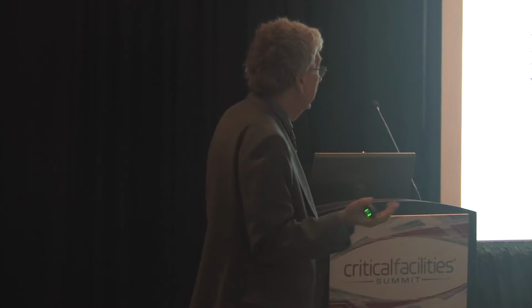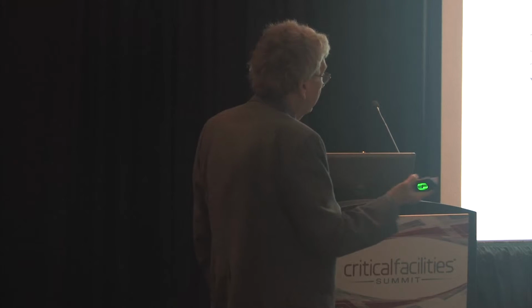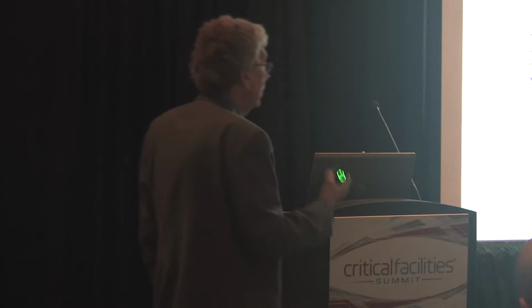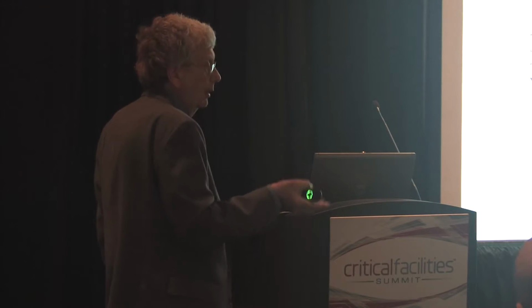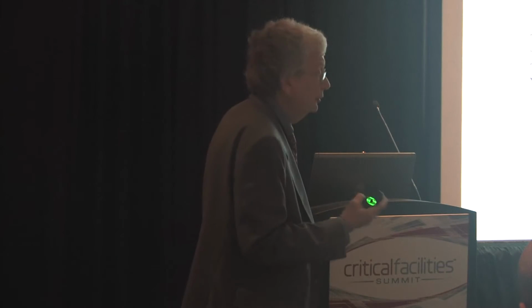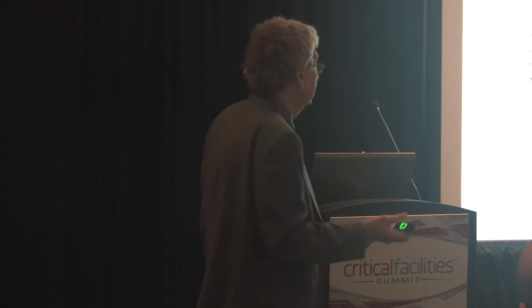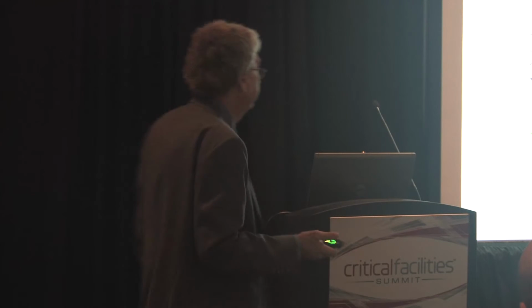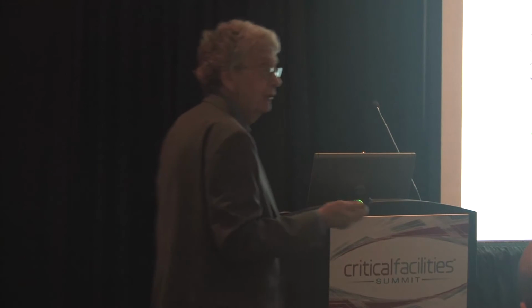However, typically UPS output is stated in kW, kVA. It's not actual energy over time. It's not a recording meter. So you can take snapshots, but not everybody runs over to the UPS and polls it every 15 minutes. So unless you've got some software doing that, which is one of the functions of DCIM, you tend to take a daily reading, whatever your particular frequency is, and if you're charting that against your daily loads, you're beginning to have at least a sense of a day or how many hours in the day, depending on how often you're doing it manually or even in an Excel spreadsheet, whatever it is that you're using. And ultimately, we can take off our shoes, calculate, and come up with a PUE.